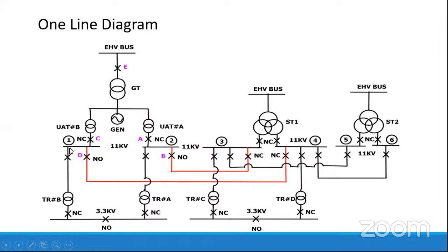Here also you can see this NO, which indicates normally open. The line from the D point to this 11 kV ST bus is normally open, and it's also open from this end from the UAT bus A. There's a three winding transformer connected to our network. In the same way, it will feed another location, or it will step down the voltage to 3.3 kV and feed power to other outgoing locations.